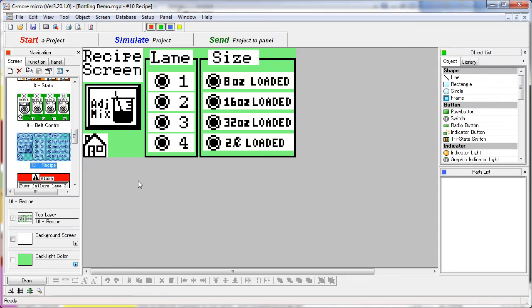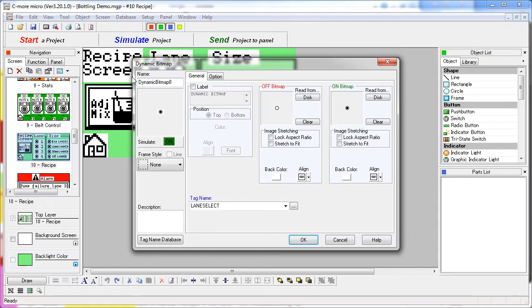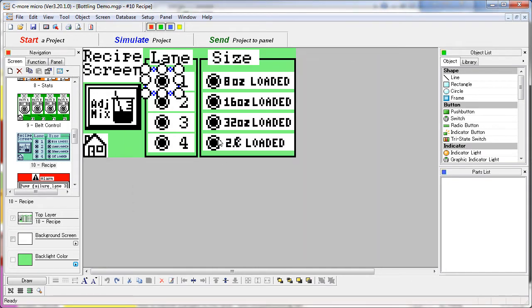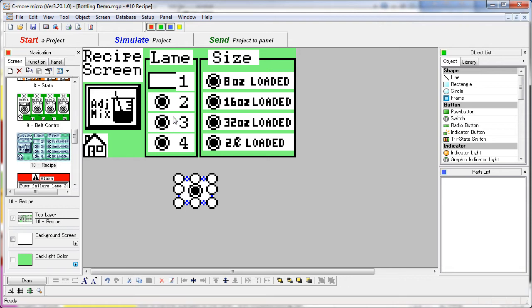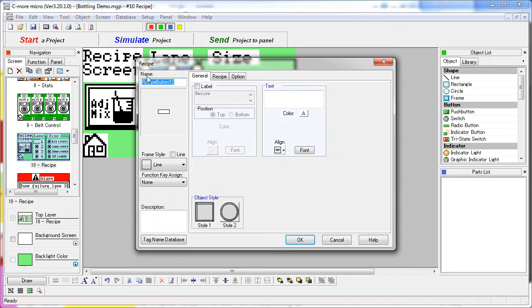First screen 10, the bottle screen. Here we have a dynamic bitmap button. Well that doesn't make any sense – a dynamic bitmap just monitors a tag – it doesn't change anything. But if we move that out of the way, we see that underneath it, there's a recipe button. It's this recipe button that's doing all of the work.